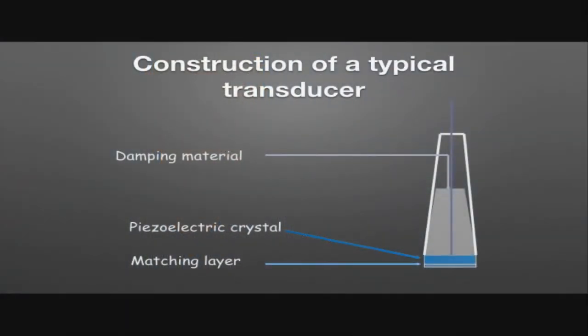These transducers contain crystals which are the source of transmitting and receiving energy. These ultrasound crystals are ground down to a thickness equal to exactly half the wavelength of the desired frequency — that's how these frequencies are made. In terms of the typical transducer, there are three main sections to discuss: the piezoelectric crystal, which has a damping material behind it and a matching layer in front of it.